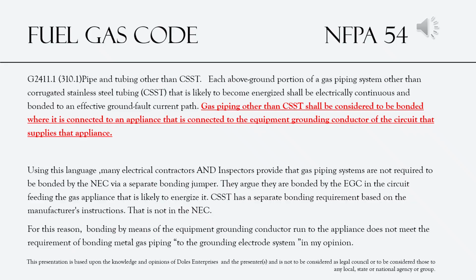Now let's look at the fuel gas code. Fuel gas code, which is NFPA 54, is typically not adopted. That's a good thing to realize. It's going to read though in G2411.1 and 310.1, pipe and tubing other than CSST. Each above ground portion of gas piping systems other than corrugated stainless steel tubing that is likely to become energized shall be electrically continuous and bonded to an effective ground fault current path. Gas piping other than CSST shall be considered to be bonded where it is connected to an appliance that is connected to the equipment grounding conductor of the circuit that supplies the appliance.